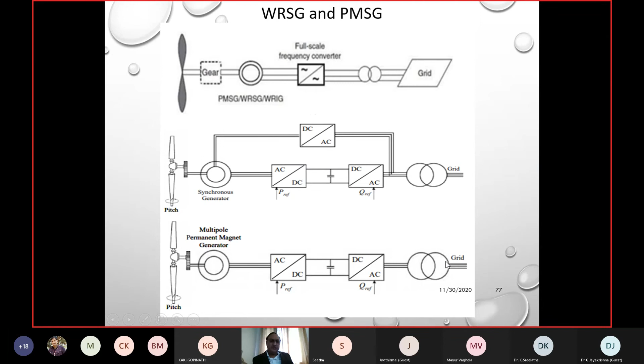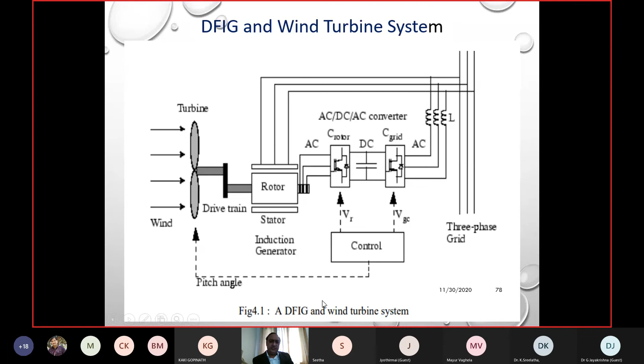So once you excite, the power generates once it is in rotation. And if it is a PM generator, then you don't have this coil. This loop is absent because permanent magnets will generate the field. Okay, so we will have only the stator. Stator generates AC power, AC to DC, filter, then DC to AC, appropriate voltage and frequency, then tap to the grid through a transformer. And for the DFIG wind turbine system, here are the details of the diagram. We have the wind turbine, the drivetrain or gearbox, then the rotor, and the rotor three phase is connected because it's a doubly fed, connected to the converter, converter to inverter, inverter through a transformer to the grid. And similarly, the stator is directly connected to the grid in a doubly fed induction generator.